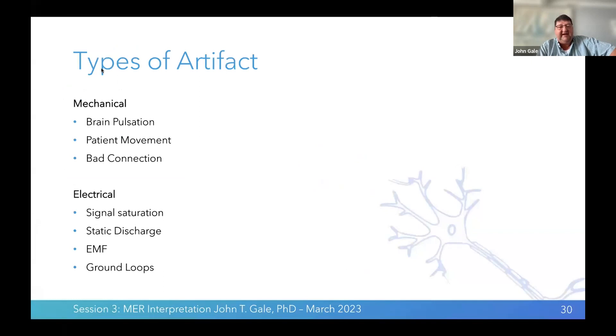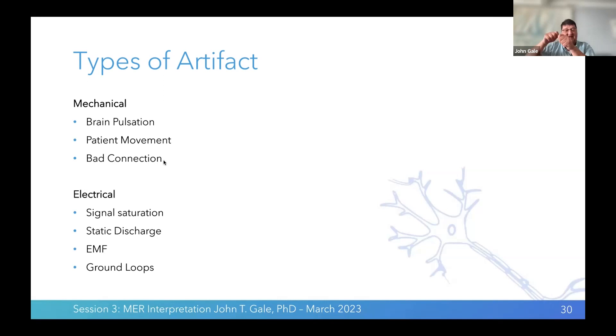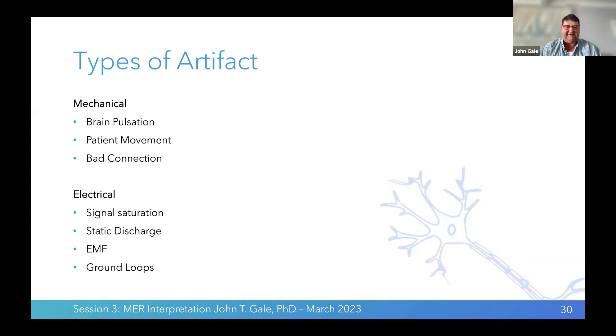Now we get into different types of artifacts more thoroughly. Mechanical artifacts include cardioballistic pulsations and patient movement — chewing, head shaking, or moving during recordings. When doing behavioral tasks, we ask patients to sit as still as possible. We can also have a bad connection or bad soldering in the cable — these are hard to troubleshoot because sometimes it looks like the signal is good, and then a very slight movement causes a contact to move and we get bad signal. The activities sometimes look like a neuron firing but they're not.